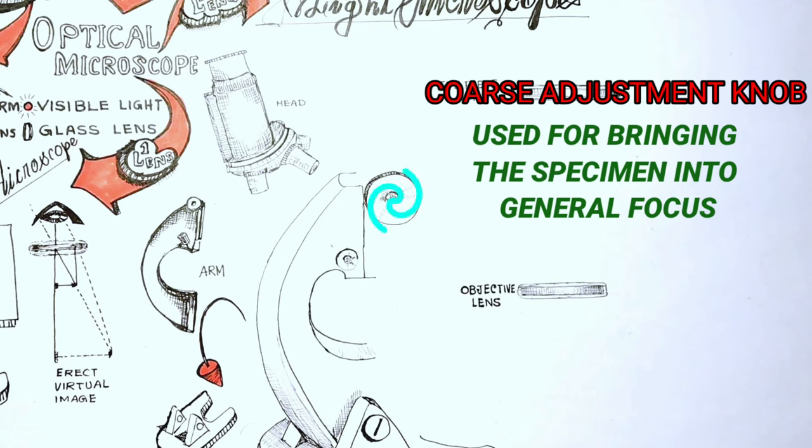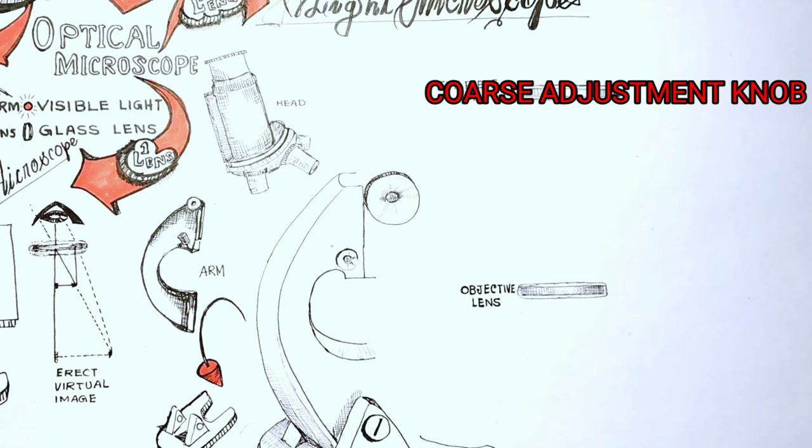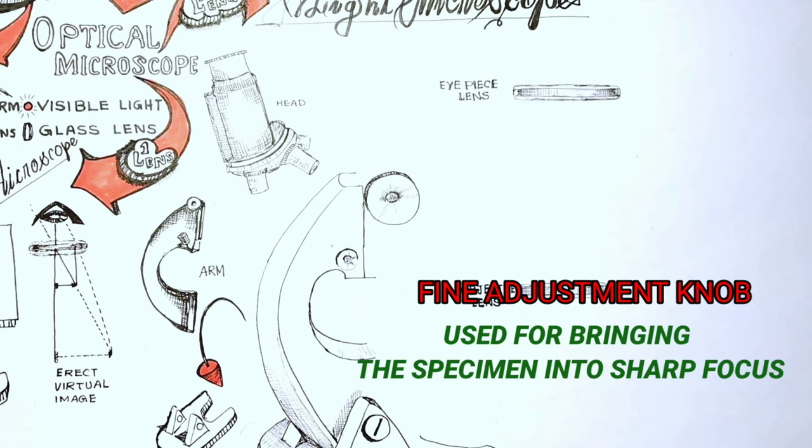But uncontrolled rotation of the coarse adjustment screw may lead the objective lens onto the slide which can result into the destruction of the specimen. So coarse adjustment knob should only be used with low power objective lenses like 4x, 10x and never with high power lenses that is 40x, 100x. The smaller knob located below the coarse adjustment knob is known as the fine adjustment knob and is used to bring the specimen into sharp focus.